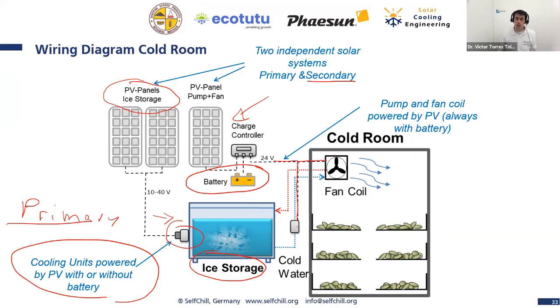Okay, so why do we need always a battery here? The reason is that at night we want to provide cooling energy, even though the compressors don't work. So we always need a battery, and this secondary system is designed in a different way than the primary system. The primary system doesn't have to have batteries, and the batteries can be small. For the secondary system, the batteries are needed and they have to be well designed so that we have good autonomy days. But I tell you already, the energy consumption of the secondary system is maximum 40 watts per day, I mean all over the day.